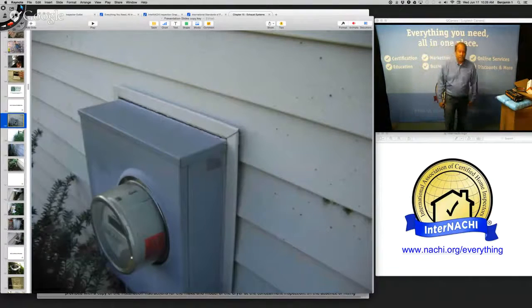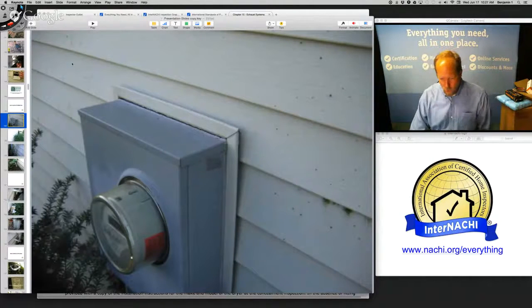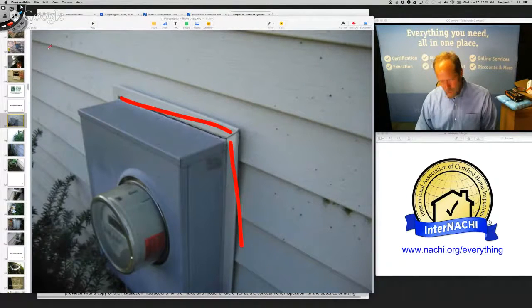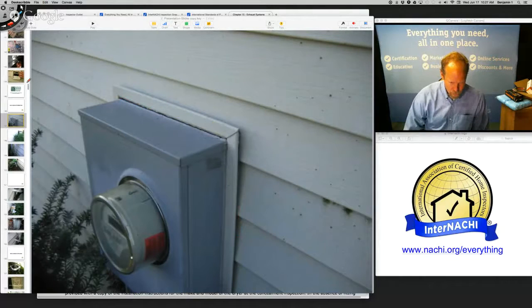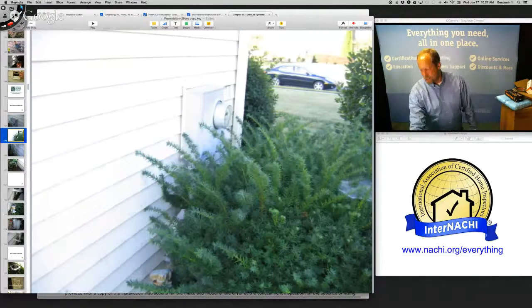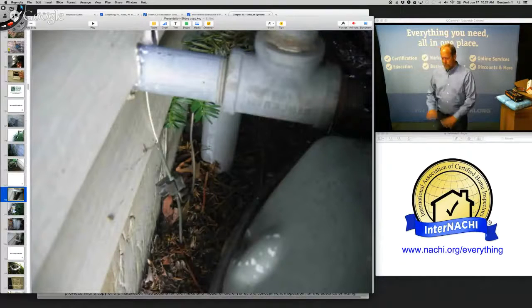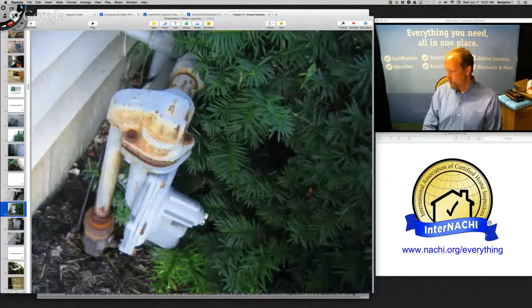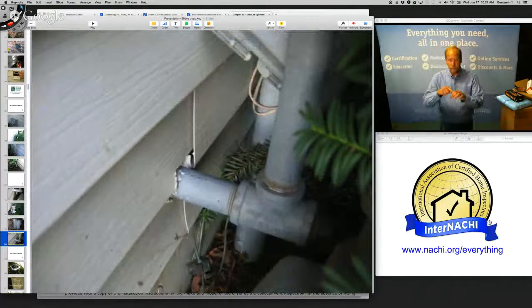On the exterior, I'm also looking at the electrical system. I don't want water penetration there — I grab the meter box and give it a little pull; some pull right off. There are inspection restrictions — I can't get to the meter. I look at the service entrance line going into the main panel in the basement, the underground conduit coming up from the ground, and the grounding wire. There's the gas meter — natural gas supplied to the house, with a pressure regulator, vent, and shutoff valve.